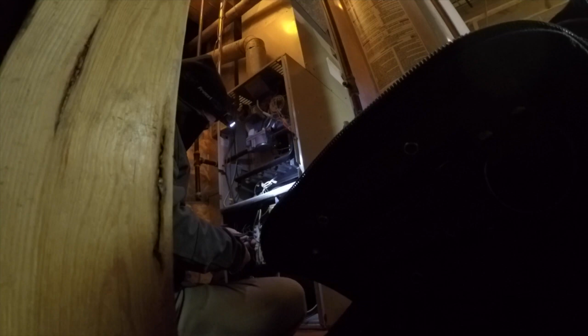It's really super hot - I'm reaching my hand back there and it feels hot. But before I make the repair, I'm going to pull out the limit. That's the piece I'm pulling out right now. I want to look at the person's heat exchanger - I don't want to change a blower motor on a furnace that has a bad heat exchanger. So I'm looking around at the heat exchanger from the top, and it looks good that way. Now I'm going to start putting that limit back in.